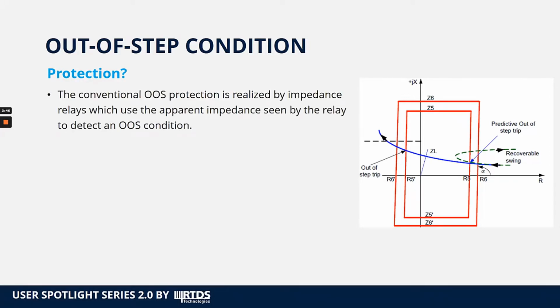Today, the conventional out-of-step protection relies on impedance relays, which use the apparent impedance seen at the relay location to detect an out-of-step condition. How this is realized conventionally is that inside the impedance relay, two characteristics are built that the relay uses to measure the trajectory and speed of the apparent impedance change and determine power swing in the network. From this, the relay can distinguish between a stable power swing or a recoverable swing, as shown on the right-hand side figure, or an out-of-step condition, whereas the swing is non-recoverable.